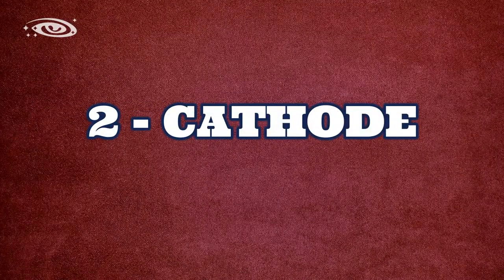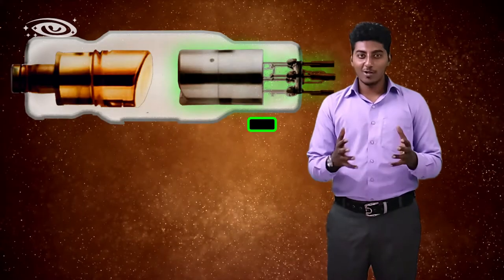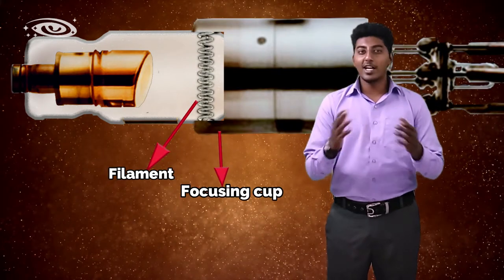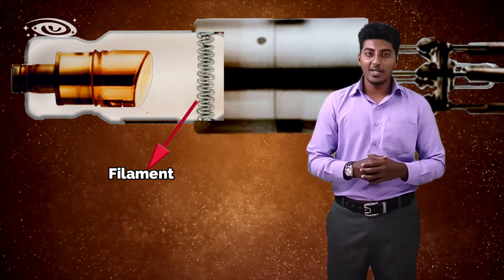Now we will see about the cathode. Cathode is the negative side of the x-ray tube and is made up of two primary parts: the filament and focusing cup.